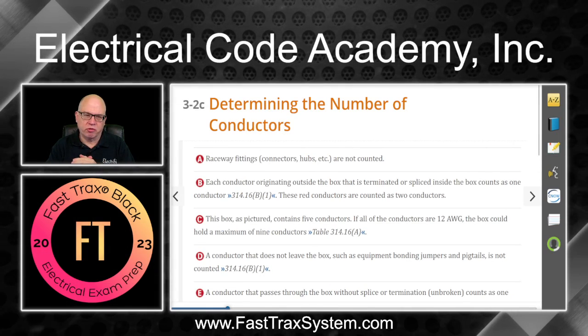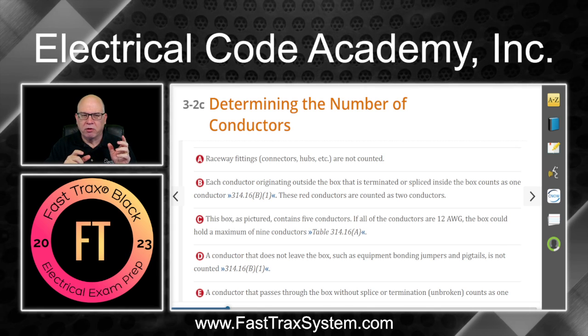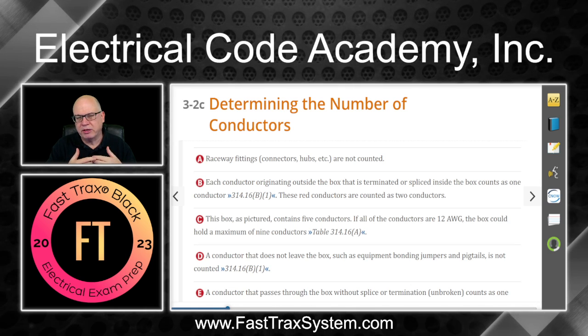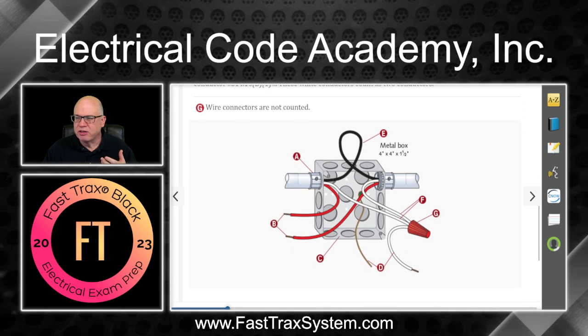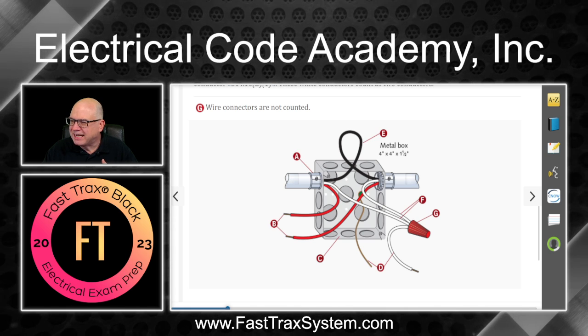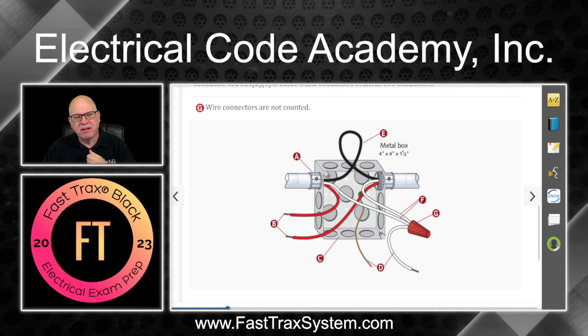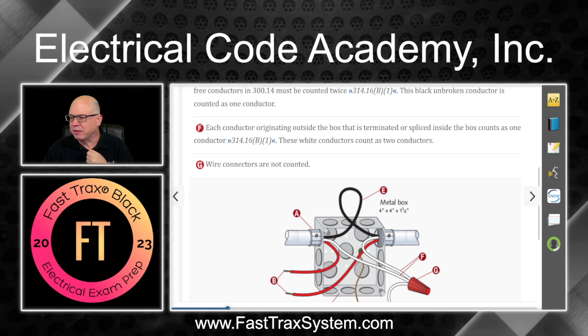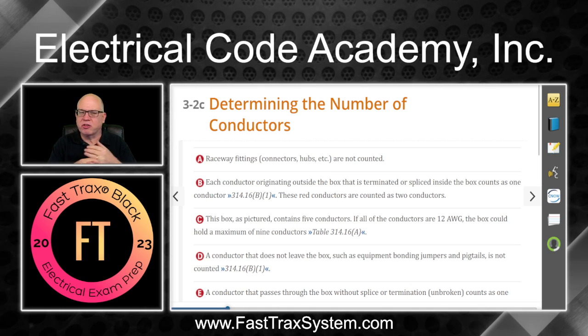Determining the number of conductors. We have to know how to look at a box and determine the conductor count. The only way we can do a volume count is to determine the conductors. This is broken down into A through G, and we have a great illustration here. This is a four by four by one and a half inch box — I believe in 314.16A that this is actually 21 cubic inches for this metal box.